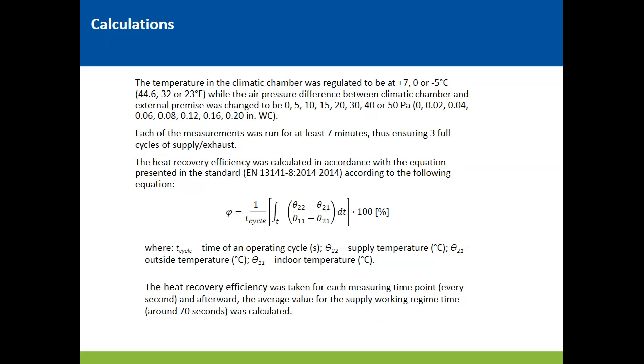Afterwards, we used the method described in European standards to calculate this ventilation heat recovery efficiency. In general, we took measurements every second for the running time of 70 seconds, and afterwards calculated the average heat recovery efficiency. We did this for several combinations of simulated outside air temperature and pressure differences. The pressure difference was in the range from 0 to 50 pascals, or in imperial units from 0 to 0.20 inches of water column, and at 3 different simulated outside air temperatures: +7, 0, and -5 degrees centigrade, or these in Fahrenheit.